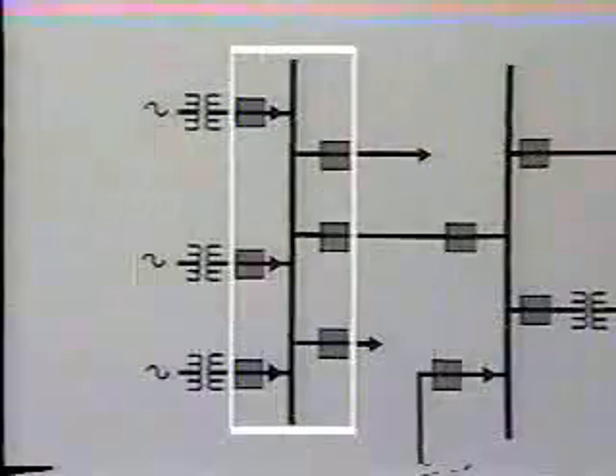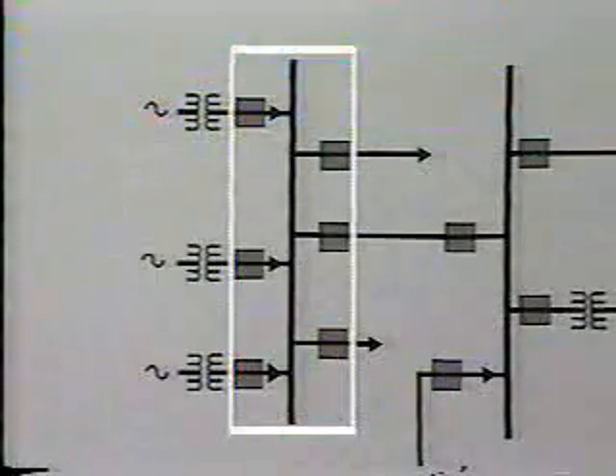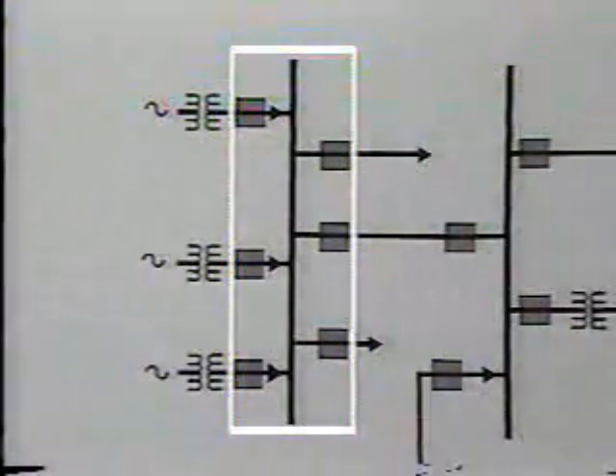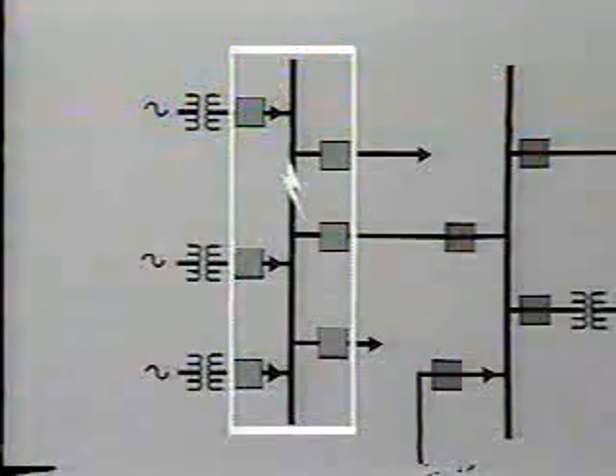The next area of protection is the bus zone. The bus will normally have several incoming and outgoing connections. After all, that is the purpose of the bus. Any fault on the bus requires that all breakers, incoming and outgoing, must be opened. So typically, the bus zone area will overlap the generator area like this.